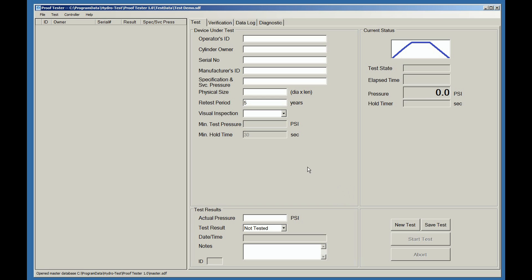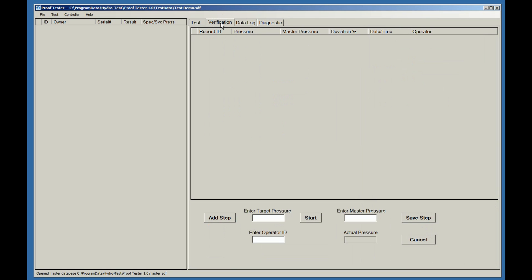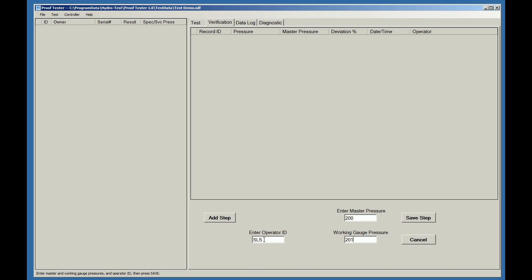Per DOT and TC requirements, we must verify the system accuracy prior to testing the cylinders for that day. Click on the Verification tab and then click on the Add Step tab. Enter an operator ID, which can be a name or initials. Enter the desired verification pressure on your master gauge, and then enter the actual pressure of the working gauge and click on the Save Step button.